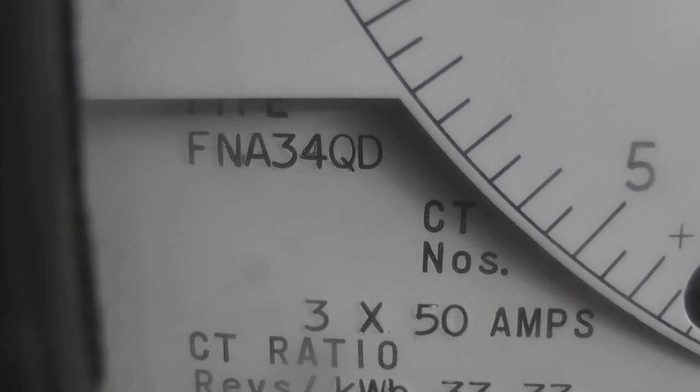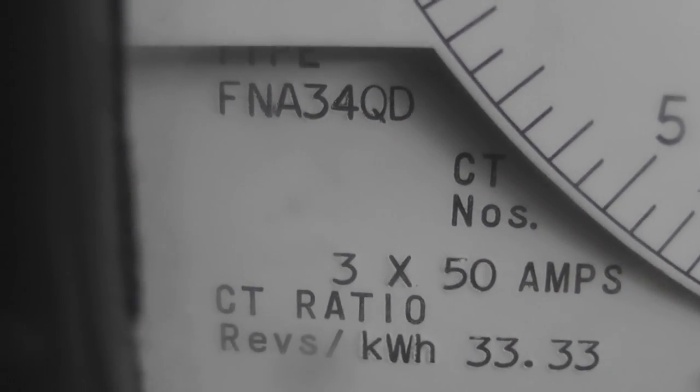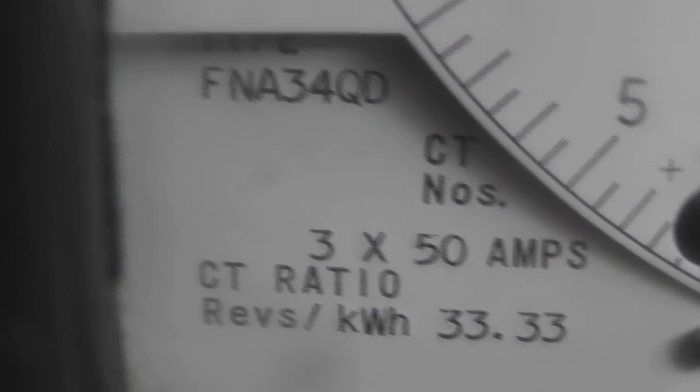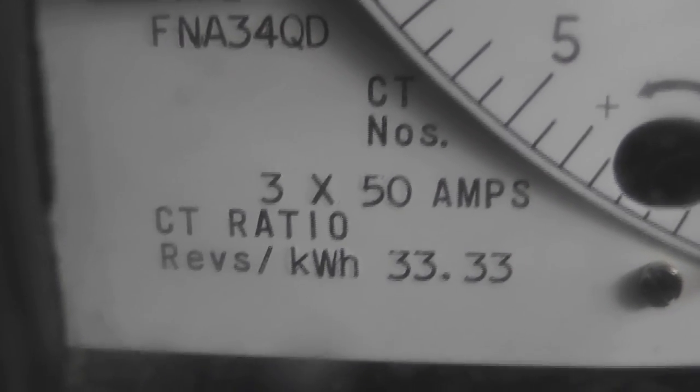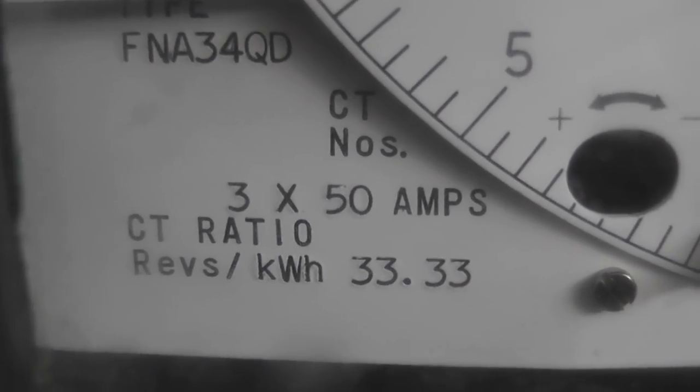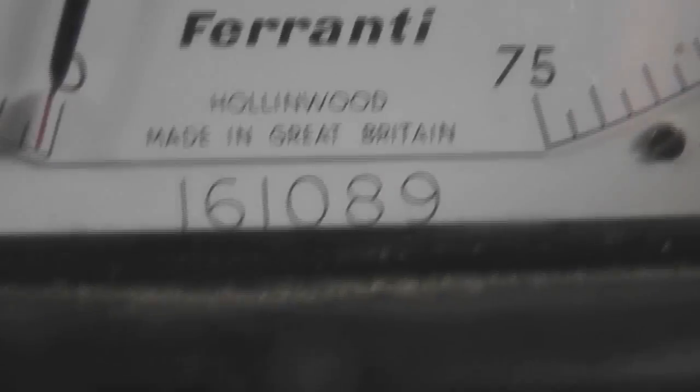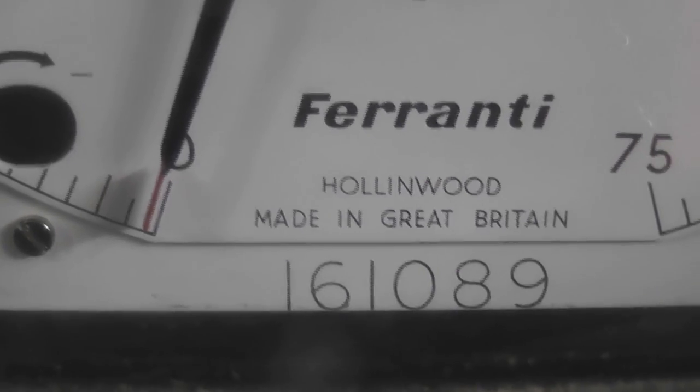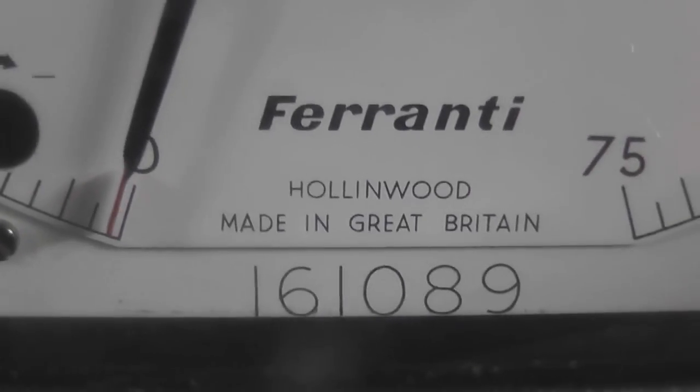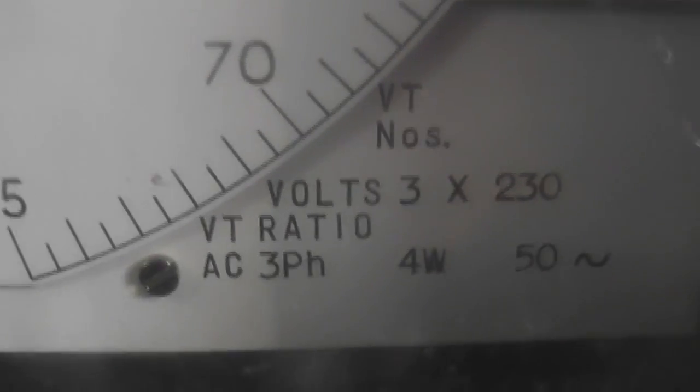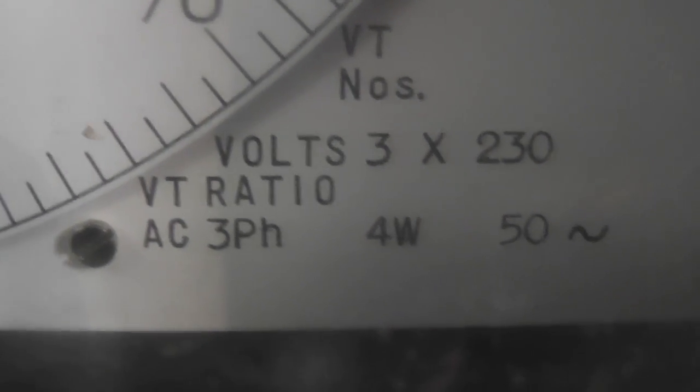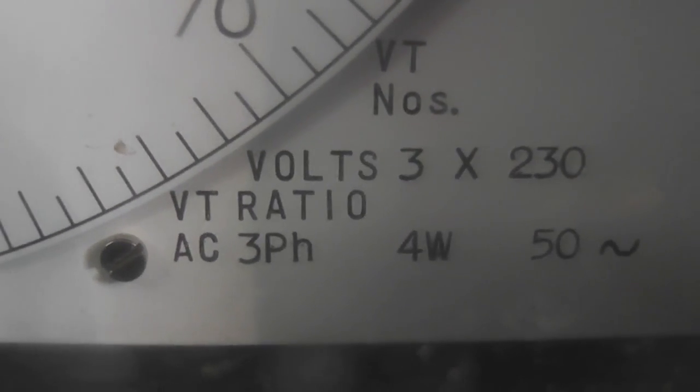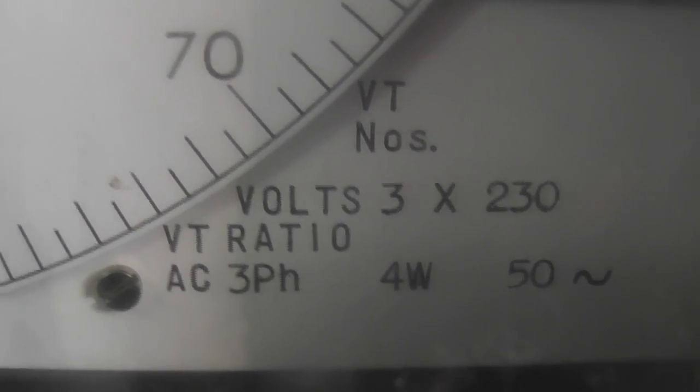The meter type is an FNA 34QD, three times 50 ampere. It's a direct reading meter 33.33 revolutions per kilowatt hour. Ferranti Hollinwood made in Great Britain and on this side is three times 230 volts. Three phase four wires and 50 hertz.